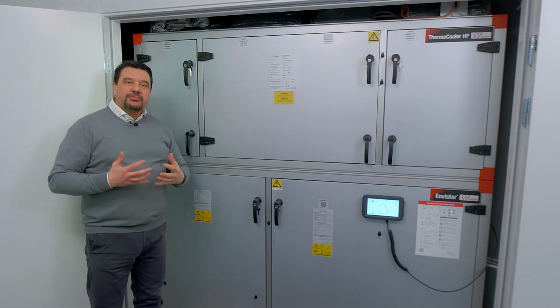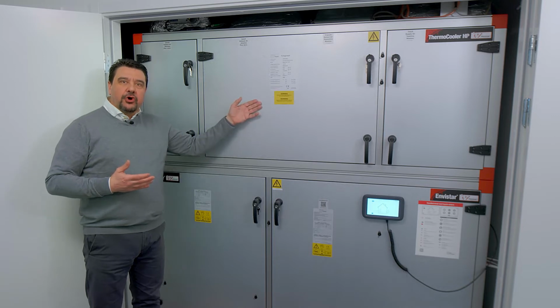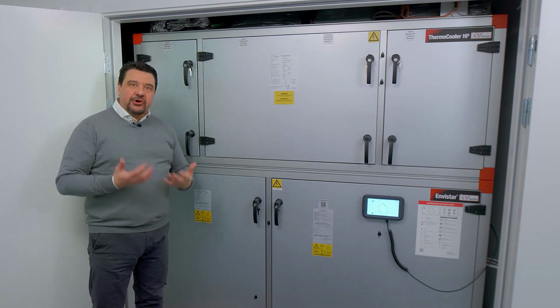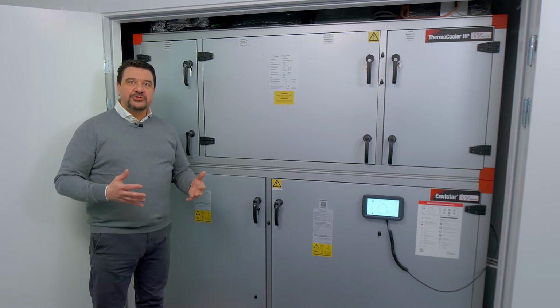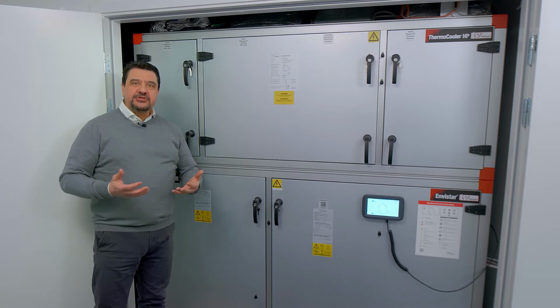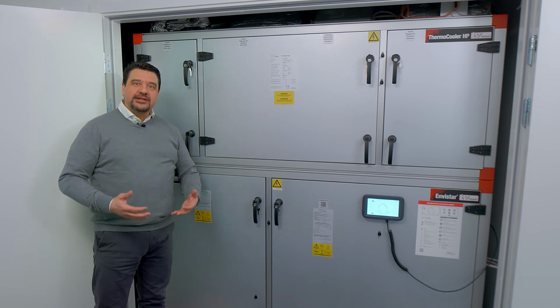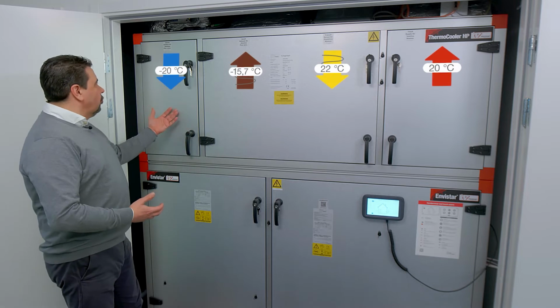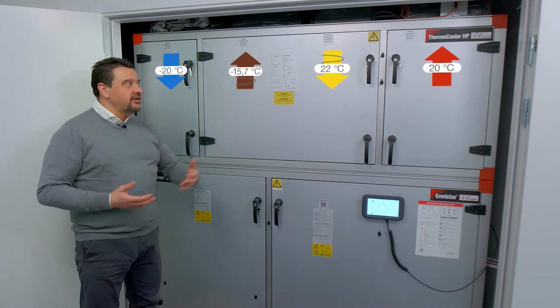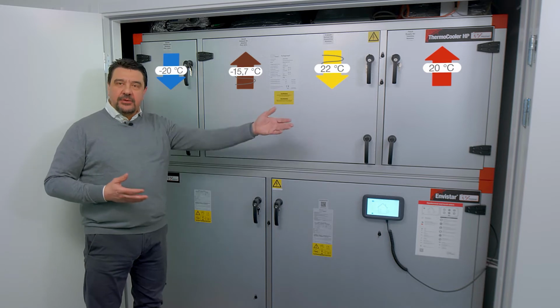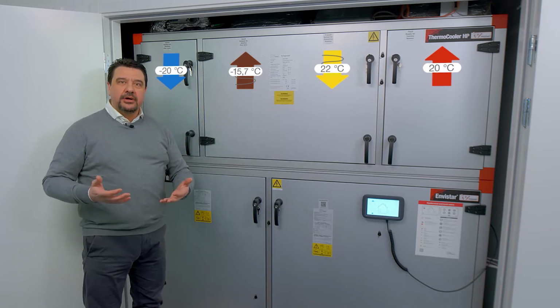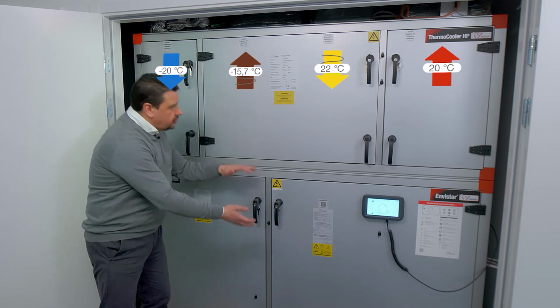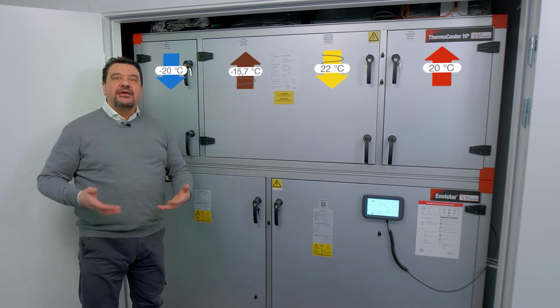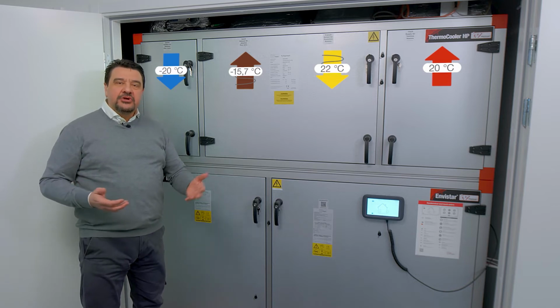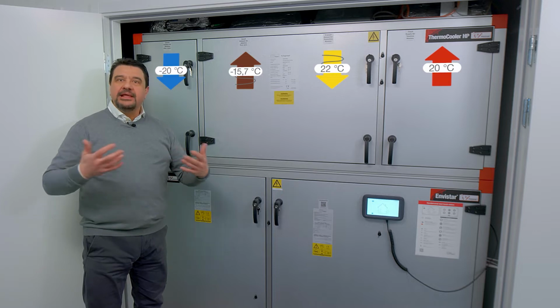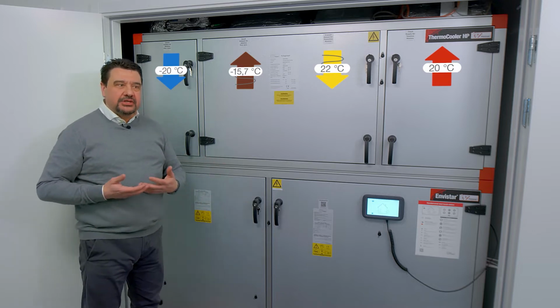And we have combined our top units with our latest innovation, Thermocooler HP, a stepless reversible heat pump, completely without defrosting needs. Which means that we can heat the supply air wintertime and we can cool it down summertime. Say we have a cold winter day of -20 degrees. We have 22 degrees in the extract and we still want to blow in 20 degrees to the room. And by combining a high efficient rotor with a heat pump, we can have an energy recovery of up to 90%. So we can blow in 20 degrees completely without heating coils or pipe systems.